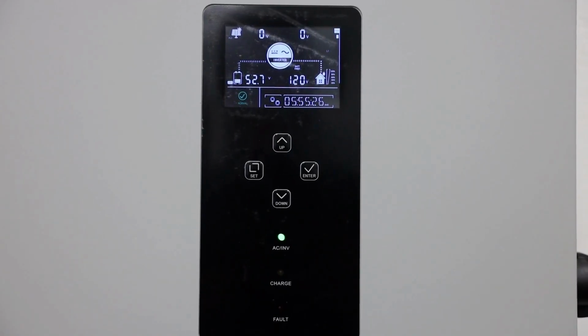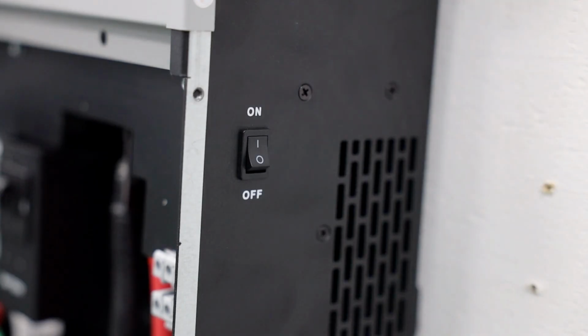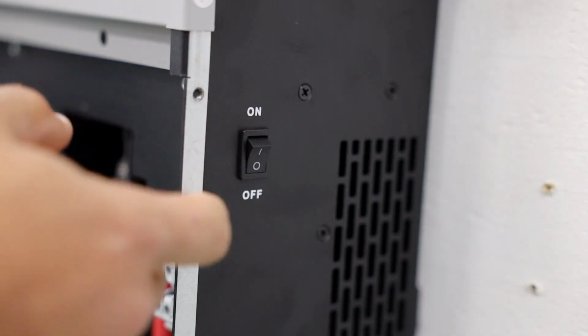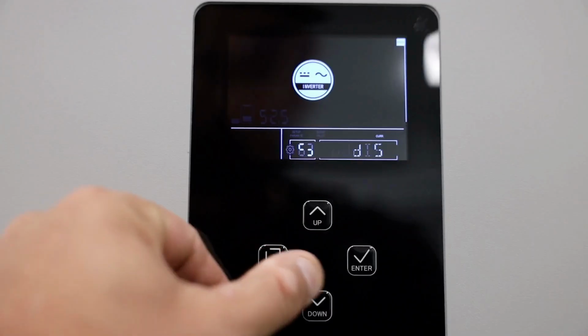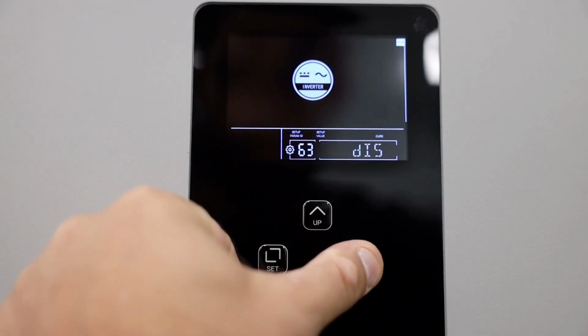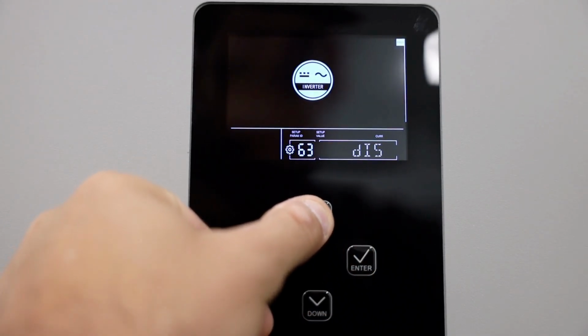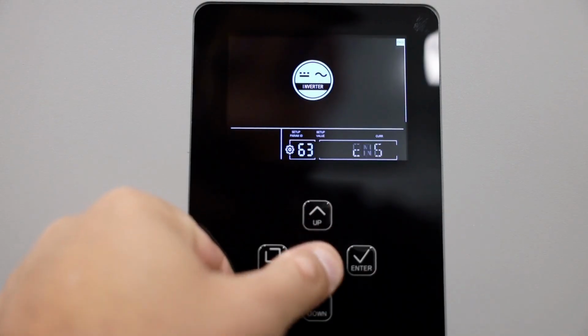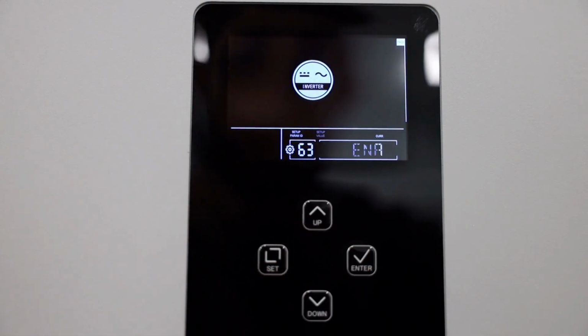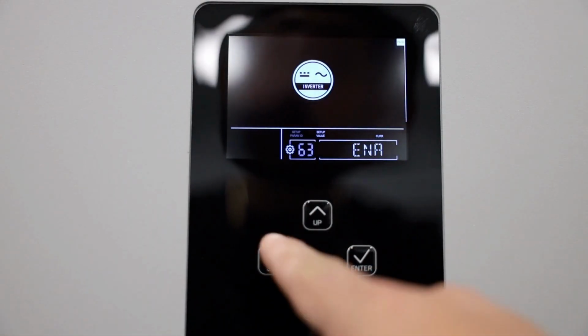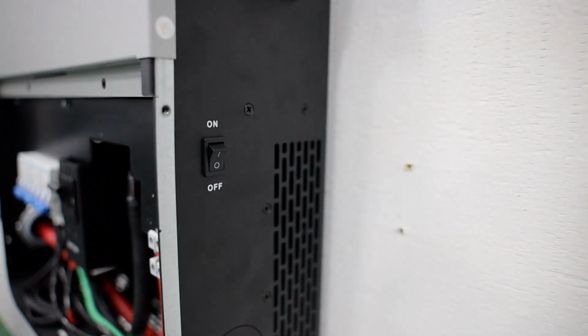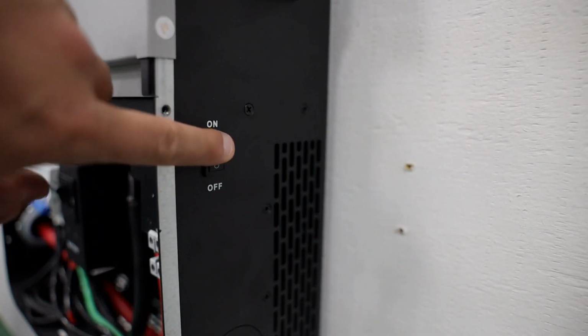The parameters are set with the Fortress Power recommended settings for the eVault Max, eFlex Max and eBoost batteries. Since this demonstration is for an off-grid configuration, turn the inverter button back to off and navigate to setting number 63 to enable the internal ground-neutral bond, as the inverter serves as the primary source ahead of the main panel. You must do this step quickly before the inverter shuts off. Turn the inverter back to the on position, and then turn the load breaker of the inverter on.